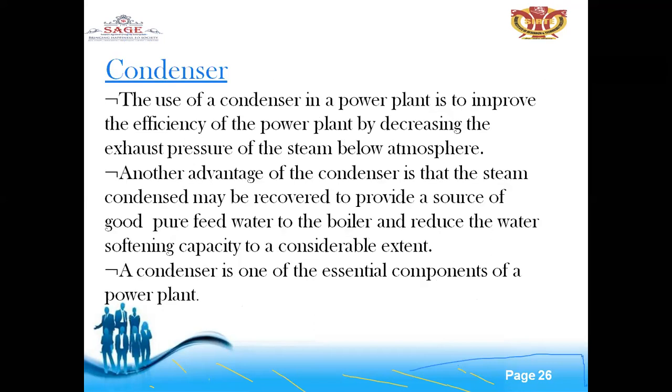कंडेंसर का इस्तेमाल पावर प्लांट में पावर एफिशिएंसी बढ़ाने के लिए होता है पावर प्लांट की, by decreasing the exhaust pressure of the steam below the atmosphere. Another advantage of the condenser is that the steam condensed may be recovered to provide a source of good pure feed water to the boiler and reduce the water softening capacity to a considerable extent.